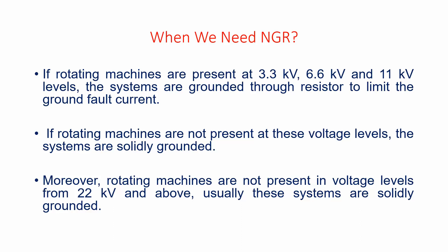So when we need NGR? If the voltage level of 3.3, 6.6, and 11 kV are connected with motors, we have to restrict the single line to ground fault current. In such a situation we need NGR.